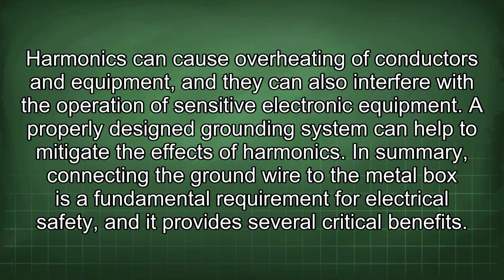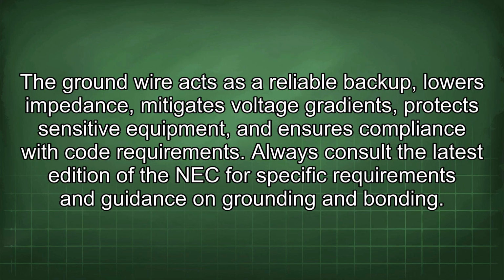In summary, connecting the ground wire to the metal box is a fundamental requirement for electrical safety, and it provides several critical benefits. The ground wire acts as a reliable backup, lowers impedance, mitigates voltage gradients, protects sensitive equipment, and ensures compliance with code requirements.